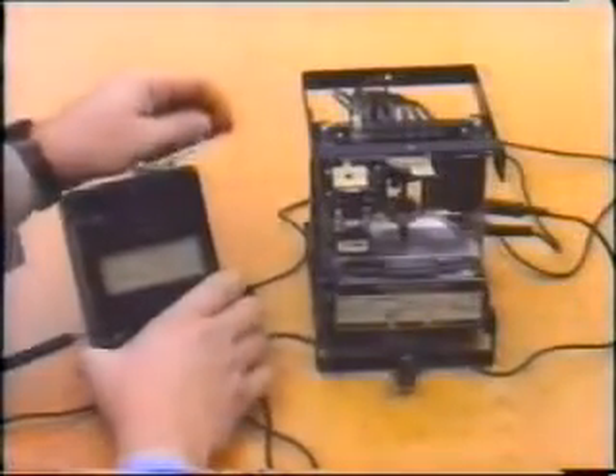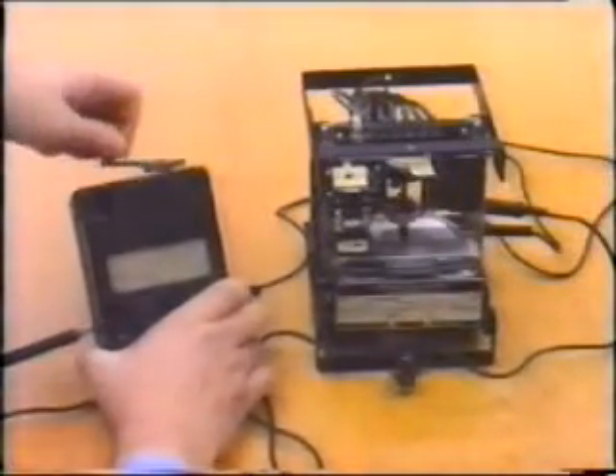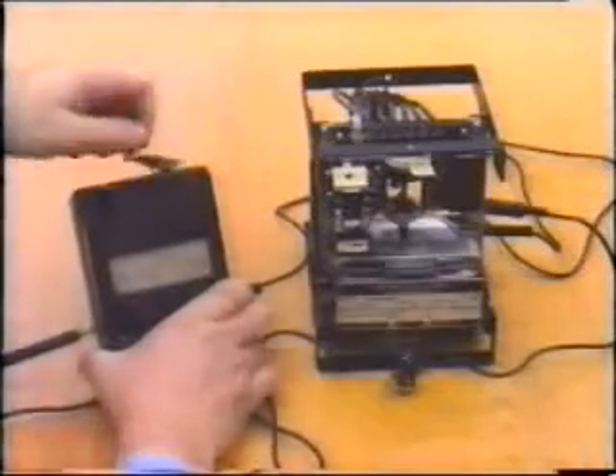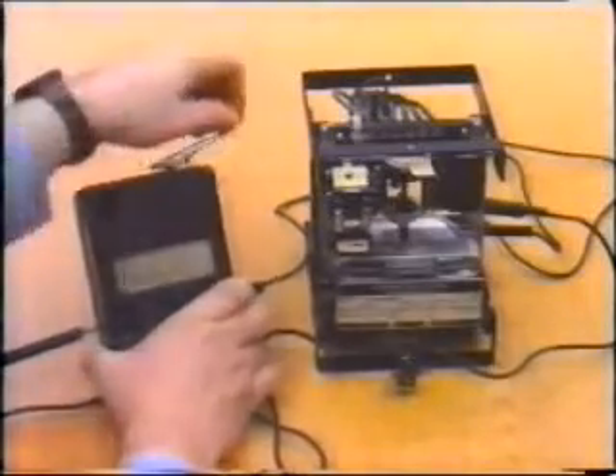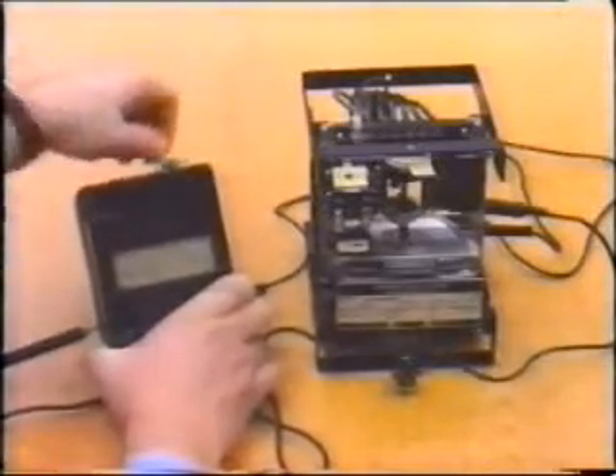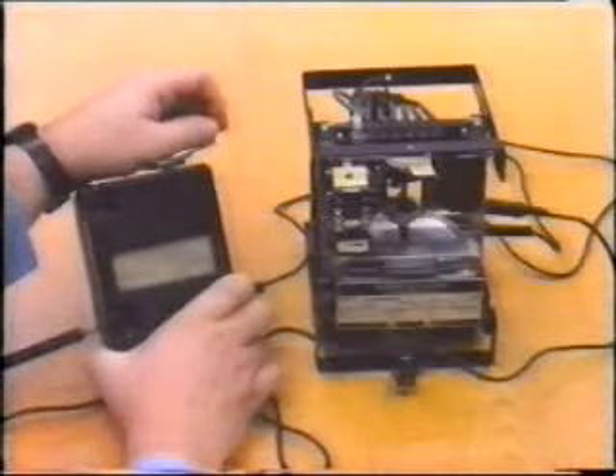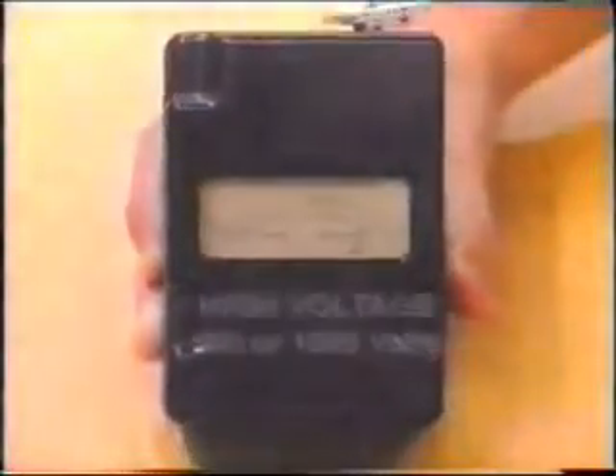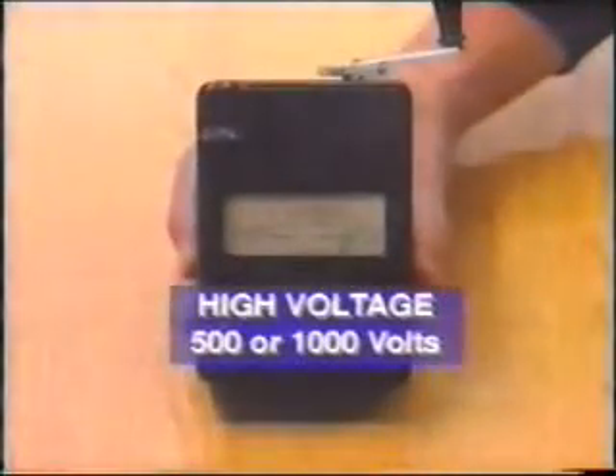While speaking of resistance, we must not forget the need to measure insulation resistance. This is, of course, a very high value of resistance that is normally measured by the megger. This instrument measures DC resistance, usually in megohms. It also produces high output voltage, thus suitable precautions must always be taken.